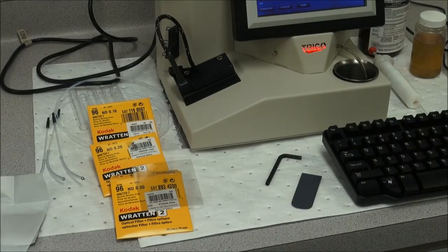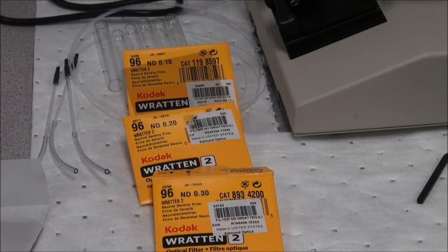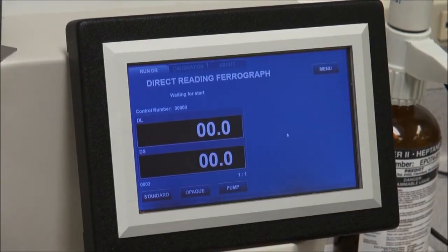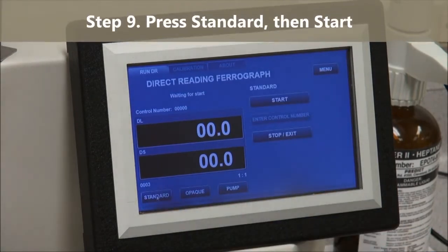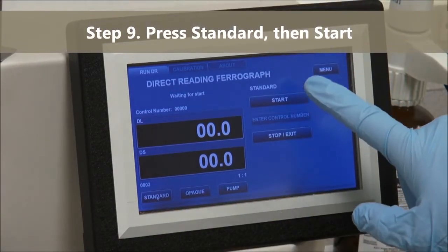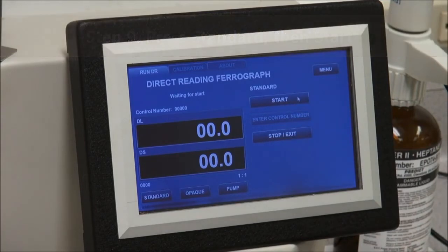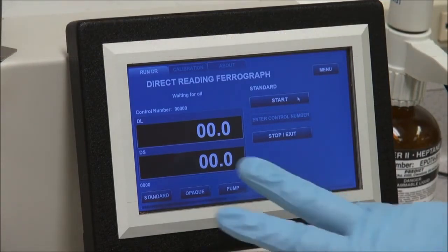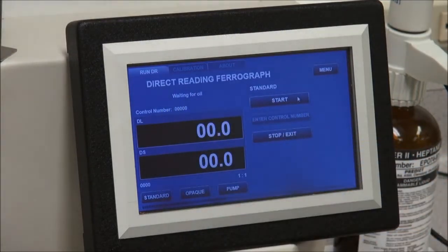In order to assure that calibration is valid, we want to use density filters. There are three different density filters, a 0.1, a 0.2, and a 0.3. We'll run a standard test with each one of these, assuring that they fall within the DL and the DS range stated in the instruction manual. To run a standard test, hit the standard button in the lower left-hand corner. Hit the start button to start the test. Waiting for oil will come up in the center of the screen.